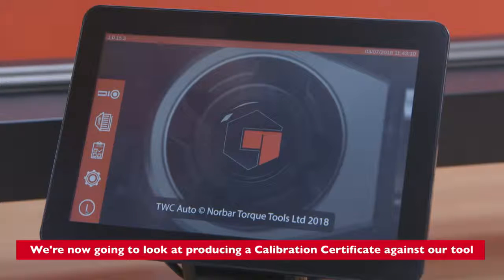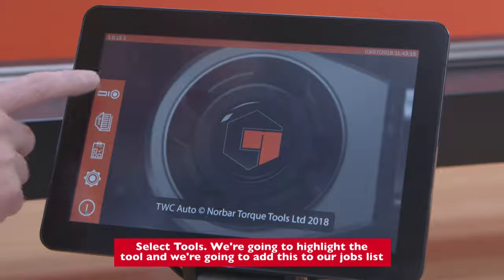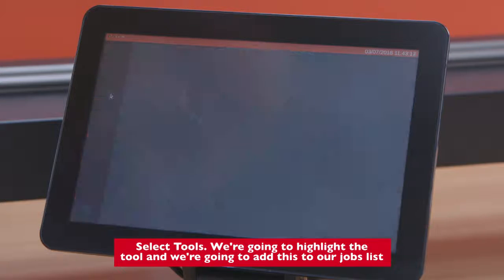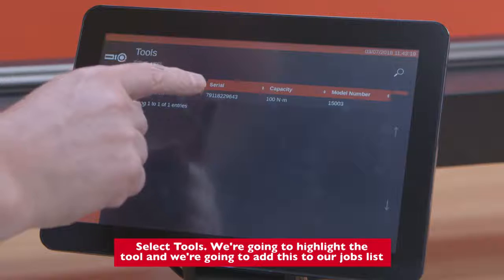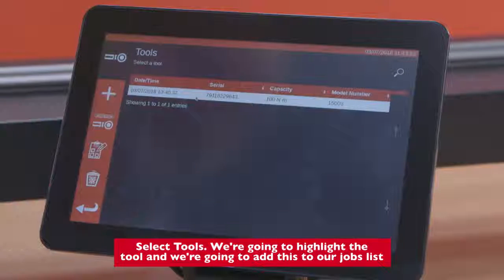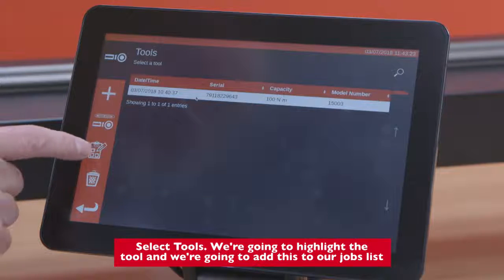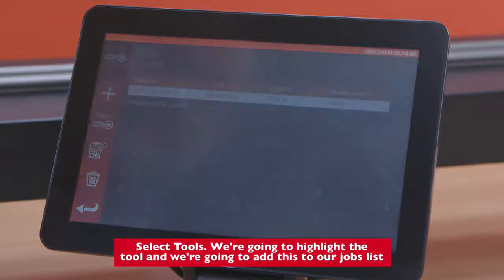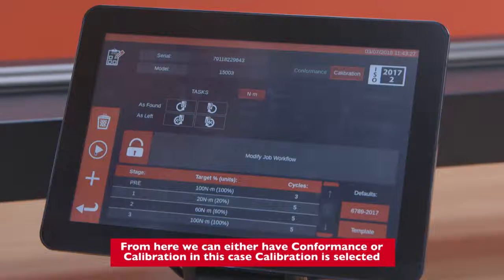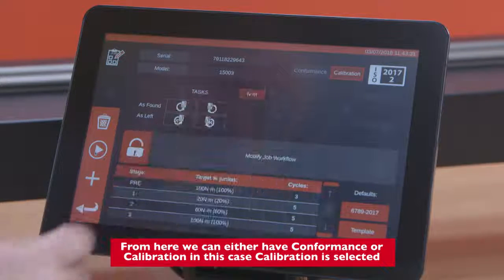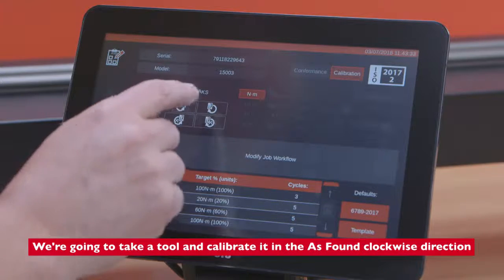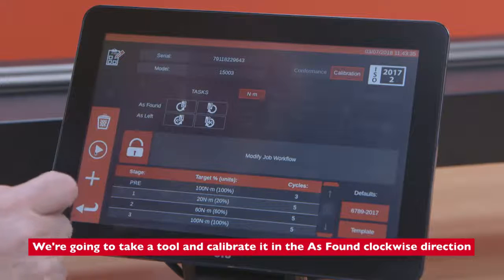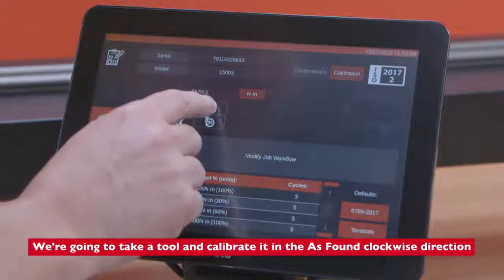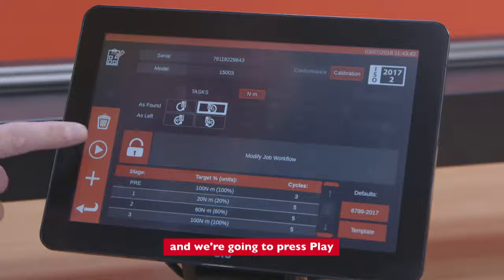So we're now going to look at producing a calibration certificate against our tool. So select Tools. I'm going to highlight the tool and we're going to add this to our jobs list. From here we can either have conformance or calibration. In this case, calibration is selected. We're going to take a tool and calibrate it in the as found clockwise direction. And we're going to press play.